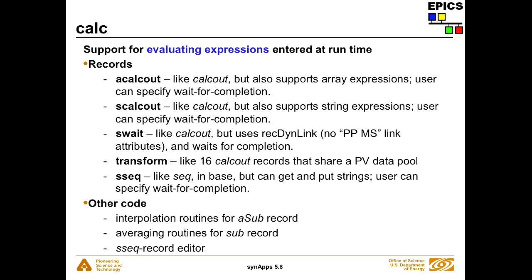Waiting for completion is important: inside an IOC you can just do a PP link and execution will be traced. But if you're writing to a different IOC, execution trace is restricted to a single IOC. So if you want to trace execution across more than one IOC, the record that bridges the gap has to do a put callback itself — and that's what these records do. There are also interpolation routines in the calc module — they do Lagrange interpolation — and a pretty nice averaging routine implemented around the sub record.